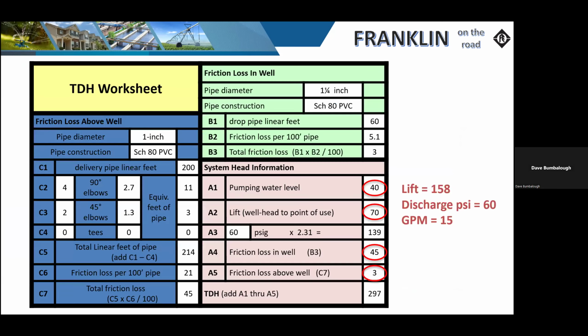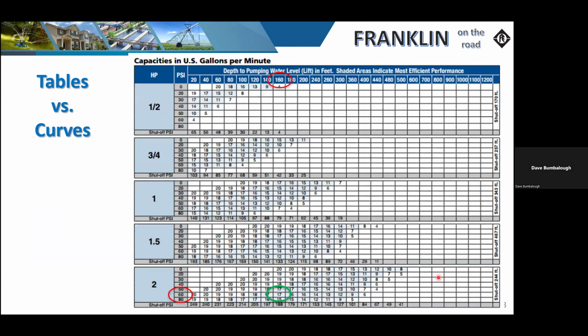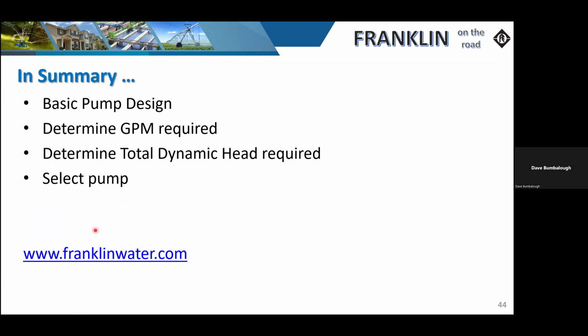So if we were to break that out, just going back to that little cheater chart, lift is 158, or pressure is 60, and we're flowing 15 gallons per minute. So if we go back to that table, it's roughly saying the same thing. The only difference is we're not looking at where the pump is set. Okay, so you have to be careful how you look at these tables versus the curves.